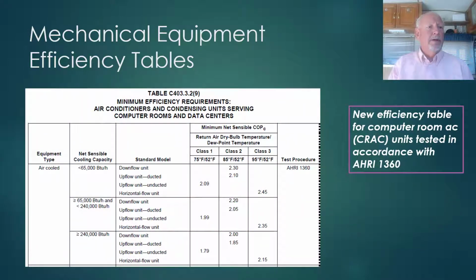Another change in the equipment tables is the addition of a table for air conditioners and condensing units serving computer rooms and data centers. This equipment is commonly referred to as CRAC units, computer room AC units, and they operate at different conditions than environmental cooling equipment. And so the efficiency of these systems is rated at different conditions. And so the code has adopted a table for minimum efficiencies based on AHRI standard 1360.